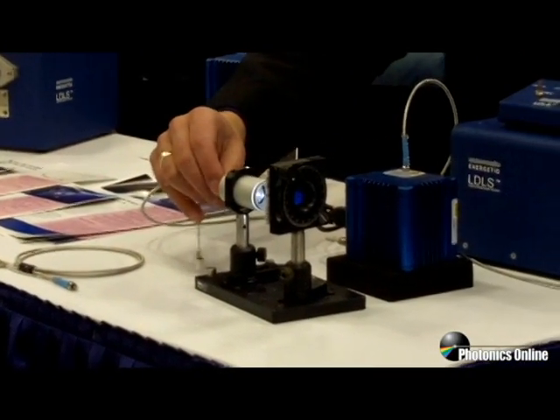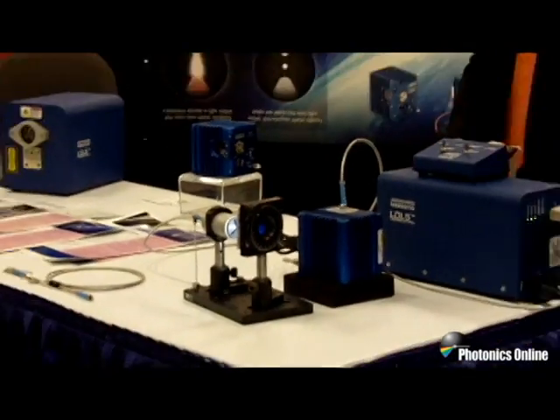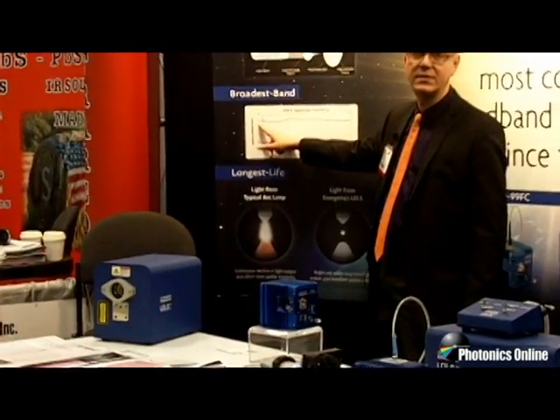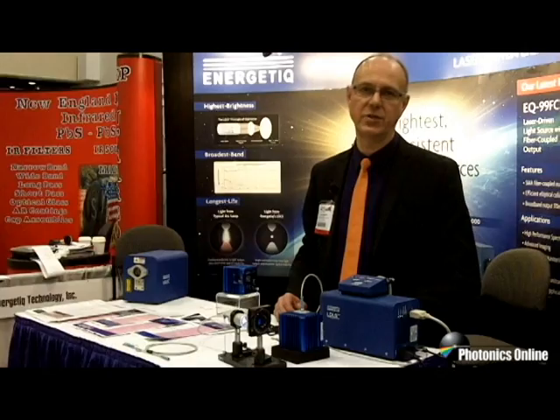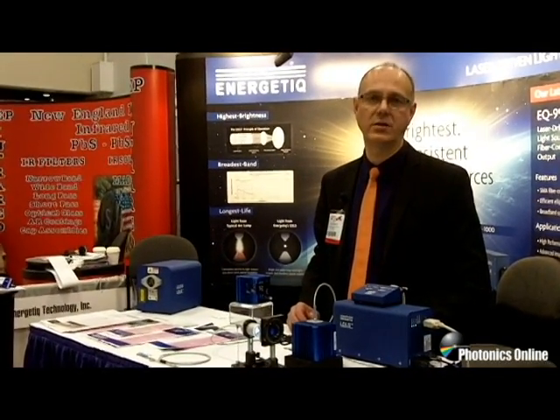The novel things about this light source are that it has a very broad spectrum. It covers light all the way from the very deepest ultraviolet, over here at 170 nanometers, all the way out into the near-infrared at 2 microns. It has a very flat spectrum and because we are using this laser-driven technology, the light source will last for an extremely long time.